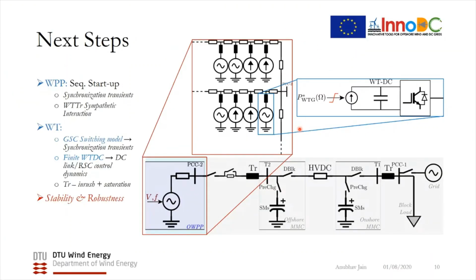This detailed model would help study how the energization transients would impact the DC link and the rotor side converter control, and also shed light on the capability of the wind turbines to deal with the transients in a controlled manner independently, and also give insight into any storage that is to be integrated to deal with any limitations. For ensuring stability and robustness of operation, some interesting studies would include disconnection of the furthest wind turbine and then reconnection, which would represent a hard switching event. And then for the soft start energization, it is important to do fault studies to ensure stability and robustness during the entire energization process. Because, for example, resonance can be triggered during the post fault voltage recovery.